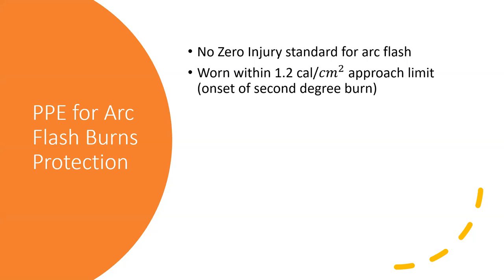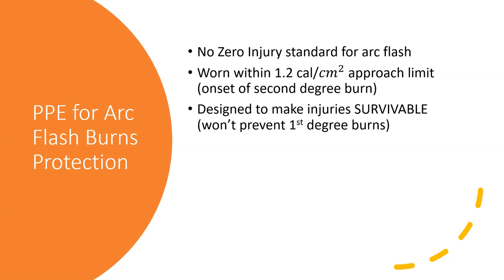Now, a first degree burn is just that top layer of the skin being burnt, which I think is called the epidermis, and that will burn at about 1 cal per square centimetre, which is the equivalent of holding a cigarette lighter maybe 1 centimetre from your finger for 1 second. That's the amount of energy there. The idea of PPE is to make the injuries survivable, but it's not going to prevent first degree burns.